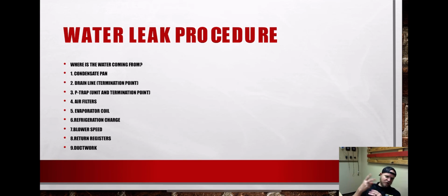Inspect your air filters, your evaporator coil, refrigeration charge. You can be condensating extra heavy if you are overcharged. It's always something to remember. That is a symptom of being overcharged. Your blower speed, you could be holding condensation onto your coil or pulling it off depending on your blower speed. Your return registers, are they plugged? Are they clean? Where are they? Have you seen them? And finally, the ductwork. Is it sufficient? Is it collapsed? Have you seen it? Same thing.